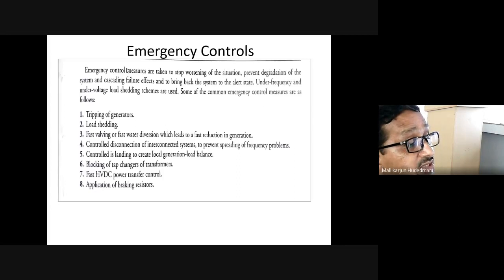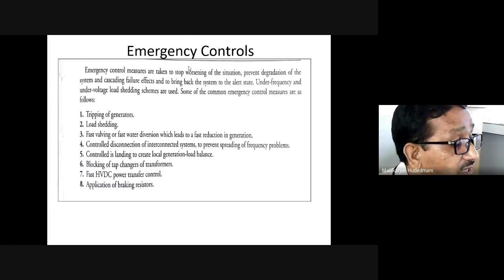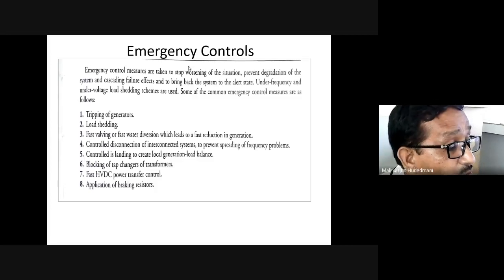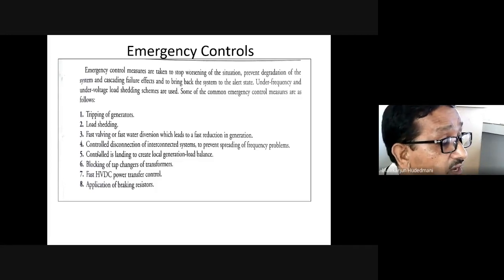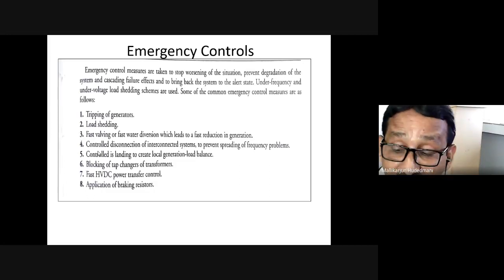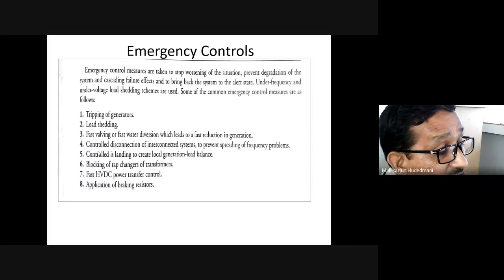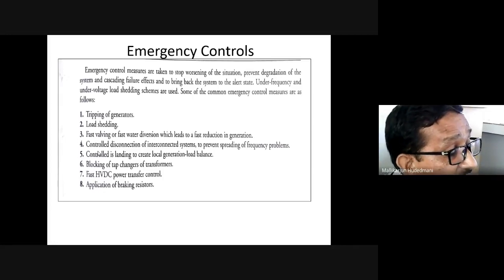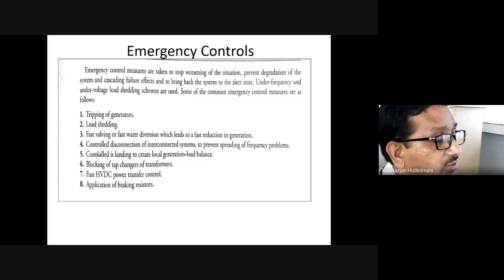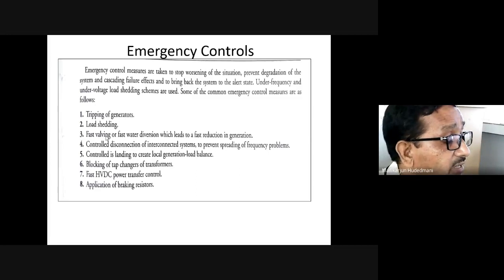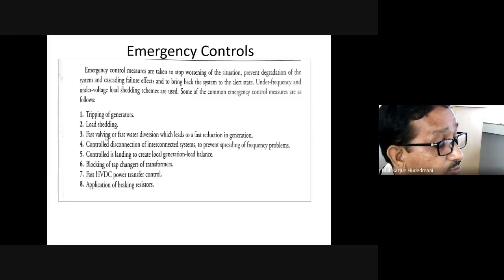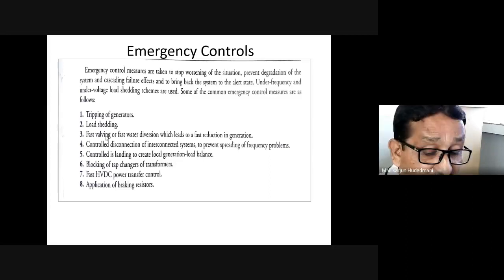Fast valving or fast water diversion, which leads to a fast reduction in generation. This is another countermeasure during this emergency situation where generation is reduced by reducing the input fuel to the turbine. I can divert the input fuel to the other side so that the input fuel hitting the turbine blade is minimized and definitely the generation output is minimized. It is to safeguard the generation and bring it to a halt state. So fast valving is to make the valve mechanism divert the water to the other side and reduce the input fuel to the turbine, so that the acceleration which is already reached will be brought down slowly.